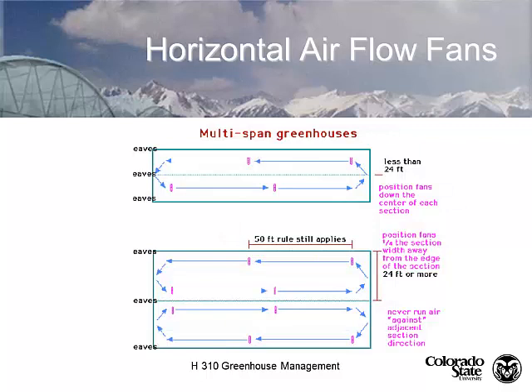In multi-span gutter-connected greenhouses where interior walls are open, we need a set of HAF fans in each bay because the gable won't allow air to move completely around. Set them so that air movement works together — for example, the top greenhouse runs counterclockwise and the bottom greenhouse runs clockwise, so the air goes together and doesn't create turbulence. It's more efficient this way — turbulence does not give more uniformity, you want the air moving together.